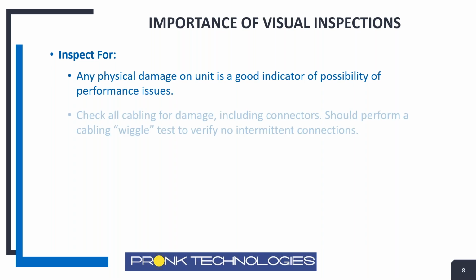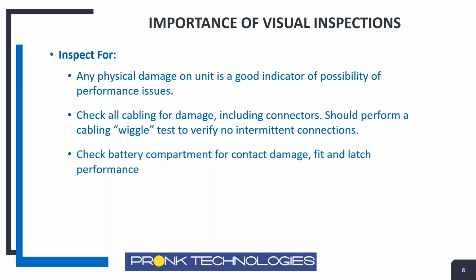Really needing to do a really good physical inspection for physical damage, not only with the hardware itself, the device itself, but you'd be amazed how many accessory problems there are: the therapy cable, the hands-free cable, damage to that cable, the connectors causing problems in use in the field. So definitely wanting to do a thorough test of all of your accessories, particularly the therapy cable, is really critical. Lots of incidents, as I mentioned, involve the battery compartment.